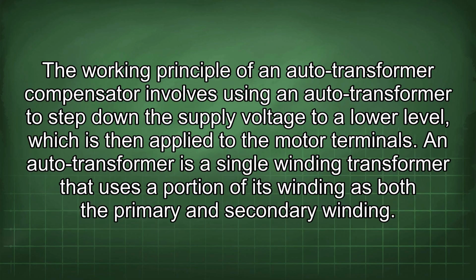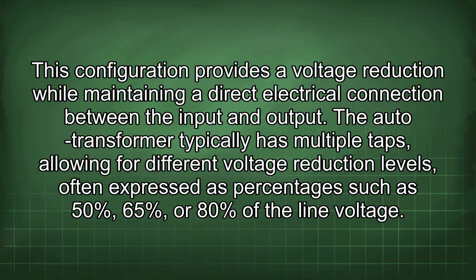The working principle of an auto-transformer compensator involves using an auto-transformer to step down the supply voltage to a lower level, which is then applied to the motor terminals. An auto-transformer is a single-winding transformer that uses a portion of its winding as both the primary and secondary winding. This configuration provides a voltage reduction while maintaining a direct electrical connection between the input and output. The auto-transformer typically has multiple taps, allowing for different voltage reduction levels, often expressed as percentages such as 50%, 65%, or 80% of the line voltage.